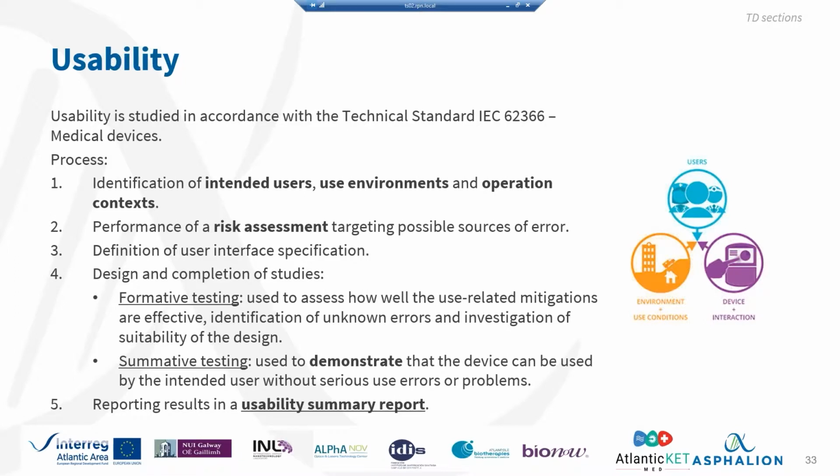First, you've got to identify who the intended users are, what the use environment is, and what the operation context is. We have insisted on this point quite a lot, but it's important to keep in mind who the intended user is. It's not the same developing a device for a lay person as for a doctor. You also have to take into account the use environment.